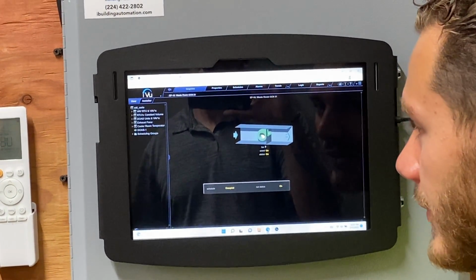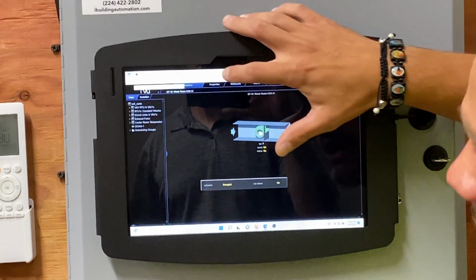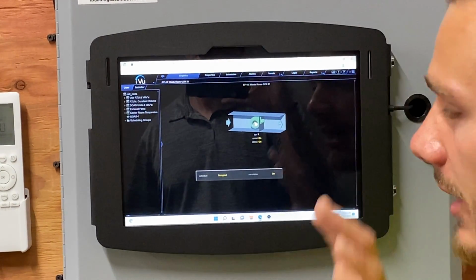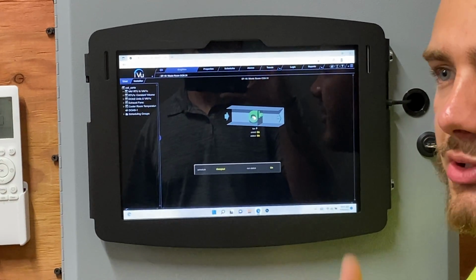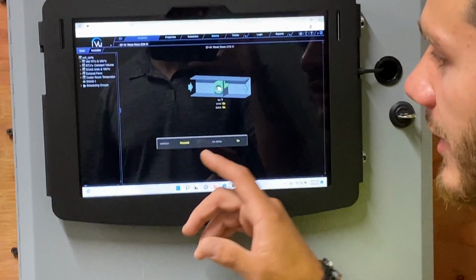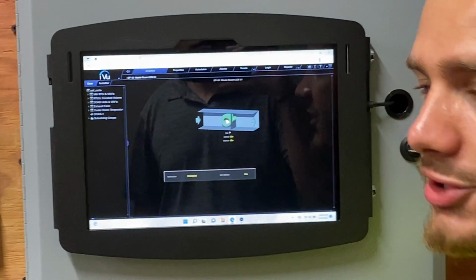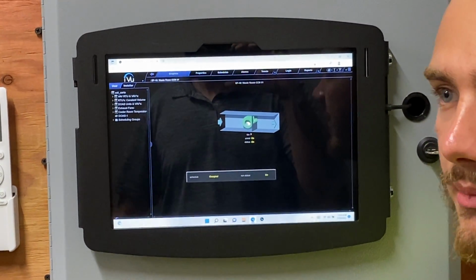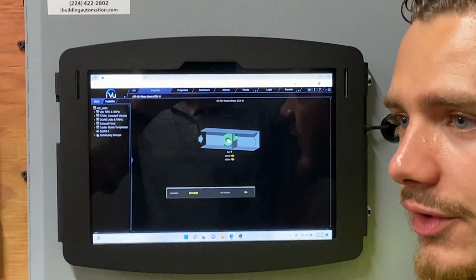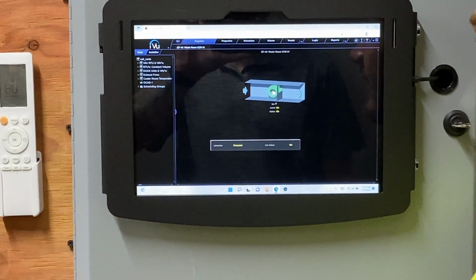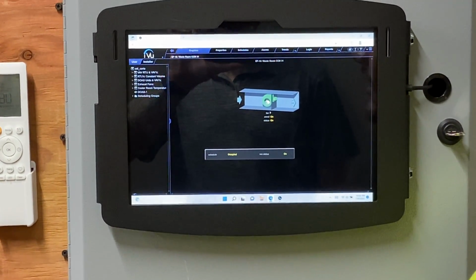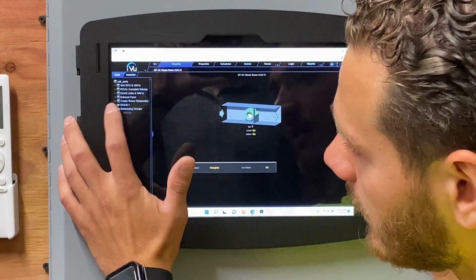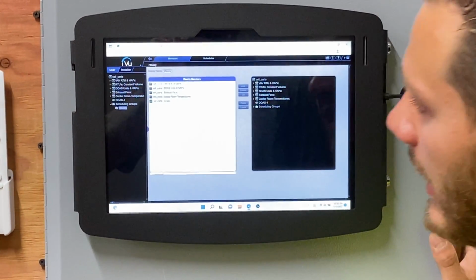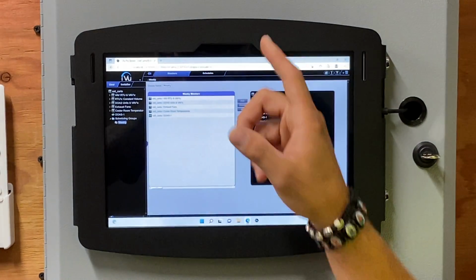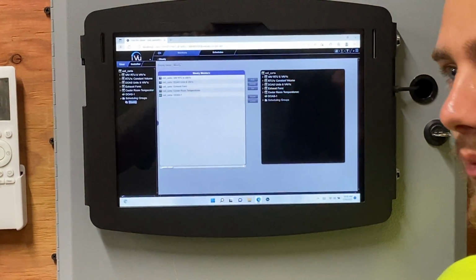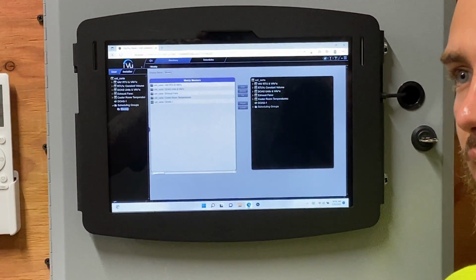Like I said, a great reference to work off of. The exhaust fans are super simple. You're not going to go into properties or make any adjustments because we're not reading values and temperatures and things like that. This is all schedule based, which I'll show you with the scheduling groups in a minute, how we can create different groups. You can create as many groups as you want for as many different pieces of equipment as you want. I've created one, I'll click on it now. I had created one scheduling group with all the pieces of equipment in the building, and we're going to go ahead and make a schedule, and everything's going to modulate off of that.